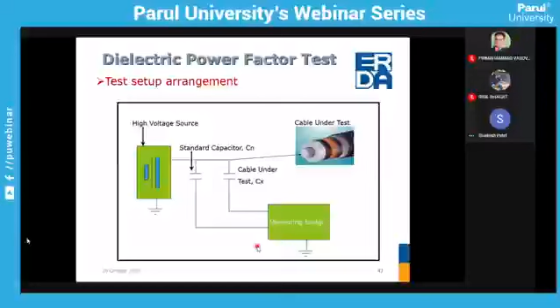As we know, the cable will undergo continuous expansion and contraction because it will carry currents. The load pattern of the distribution sites may not be constant every time. There will be slight fluctuations of currents, decrease, increase, decrease. Because of these fluctuations of the load patterns, the cable continuously undergoes contraction, expansion, correct? If the load is more, the cable conductor will be heated more. During low load conditions, the cable conductor will cool down, so contraction and expansion will be there.